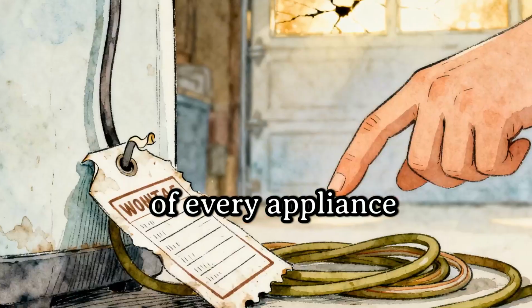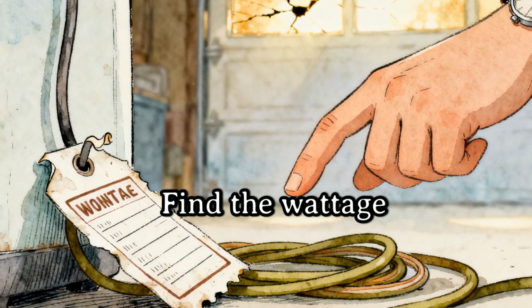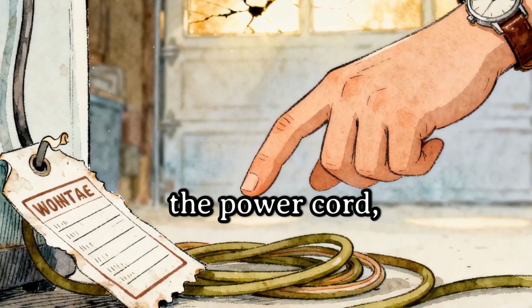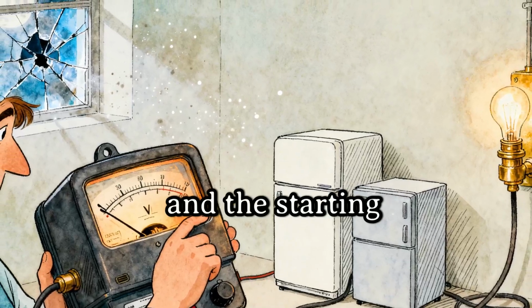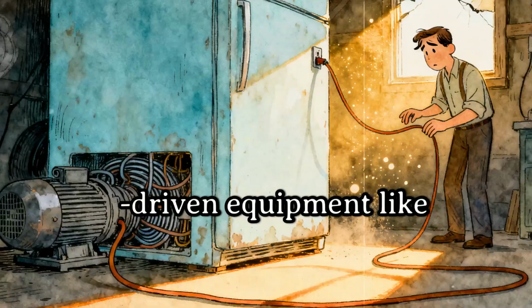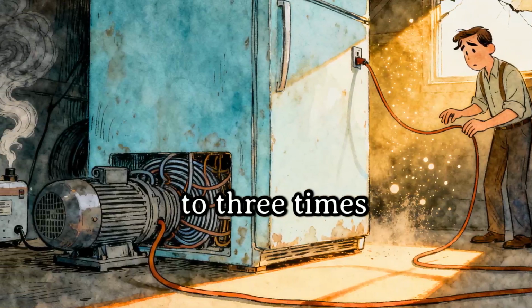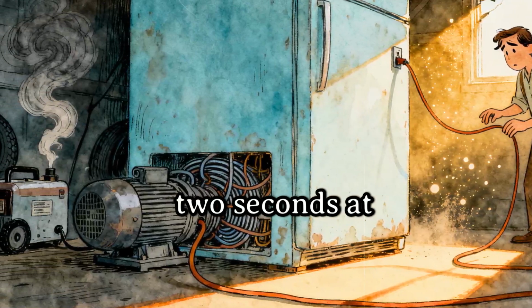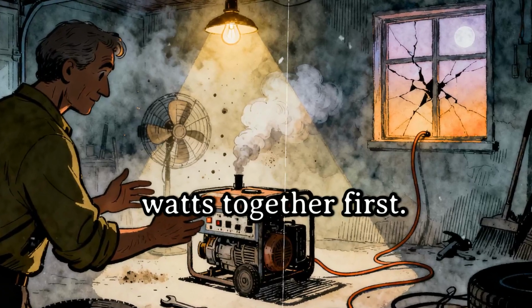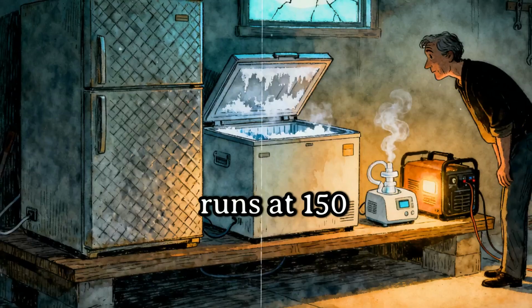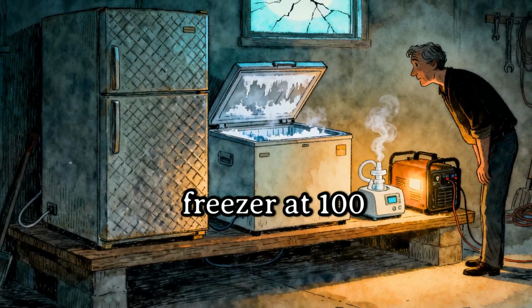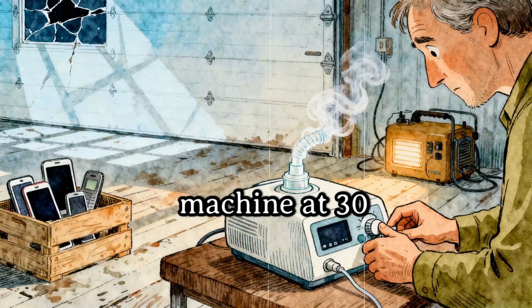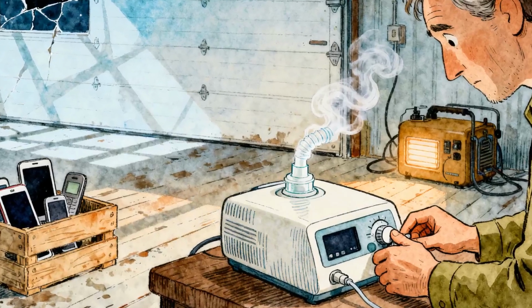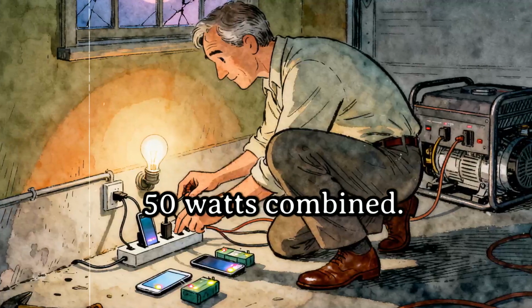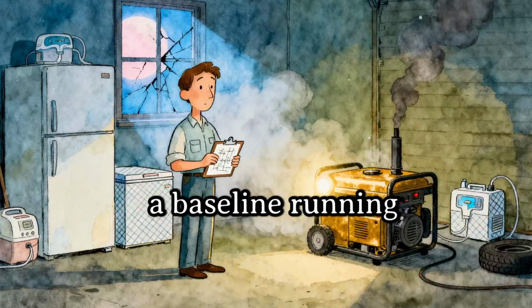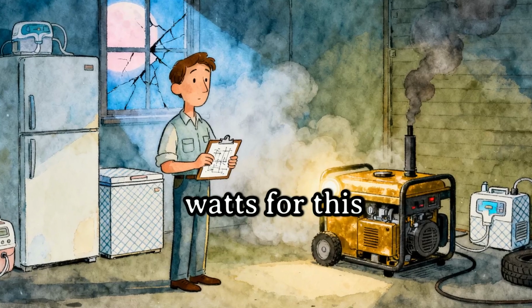Make a list of every appliance you plan to power. Find the wattage label, usually on a sticker near the power cord, and note both the running watts and the starting watts, because motor-driven equipment like refrigerators draw 2 to 3 times their running wattage for the first 2 seconds at startup. Add your running watts together first. A typical refrigerator runs at 150 watts, a chest freezer at 100 watts, a CPAP machine at 30 to 60 watts, phone and device charging at roughly 50 watts combined. That gives you a baseline running load, call it 400 watts for this example.